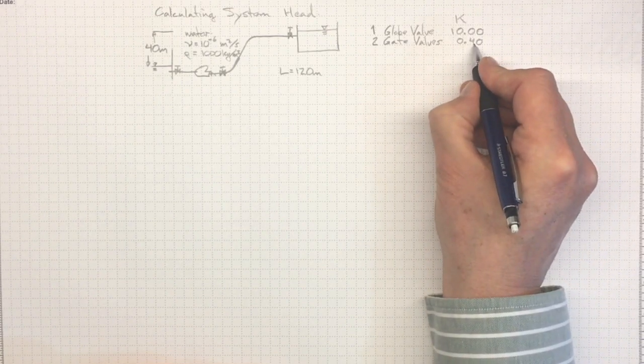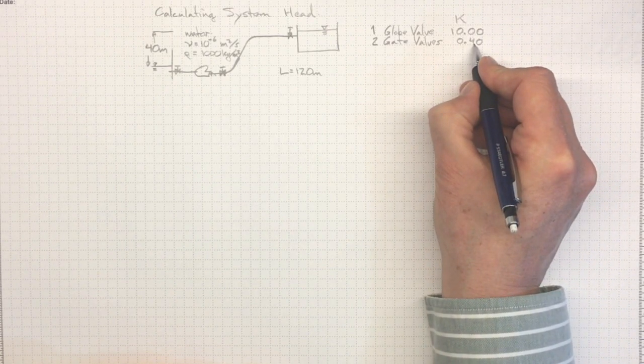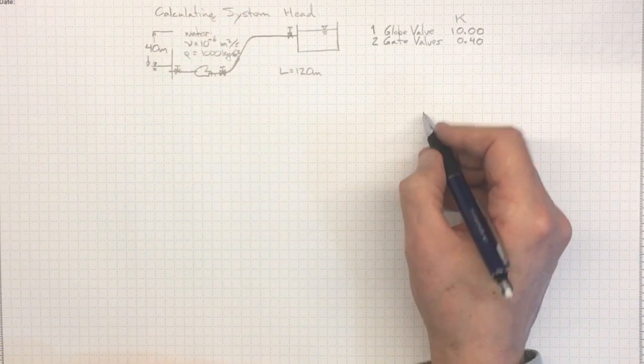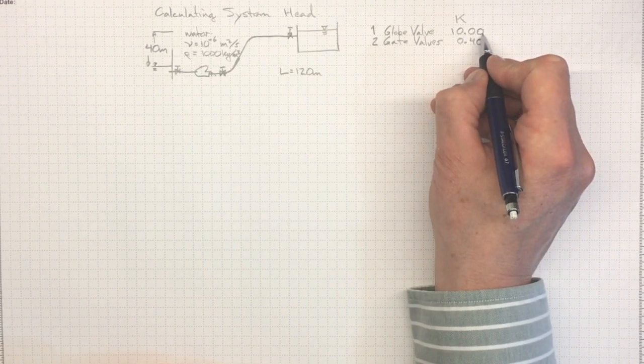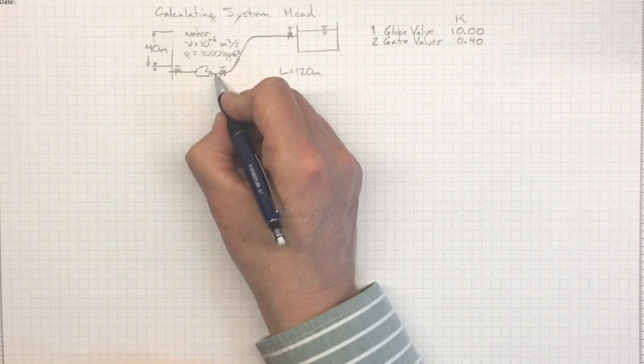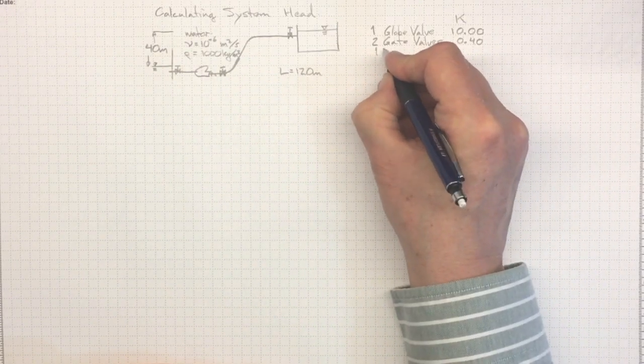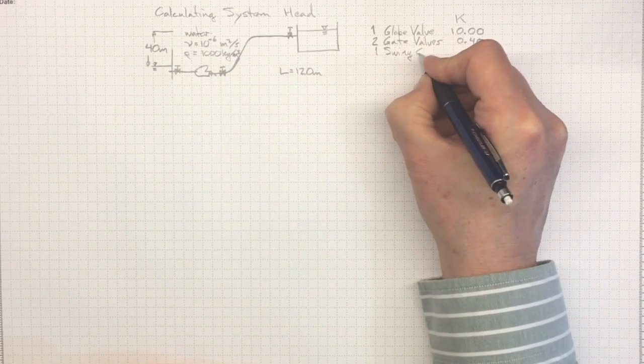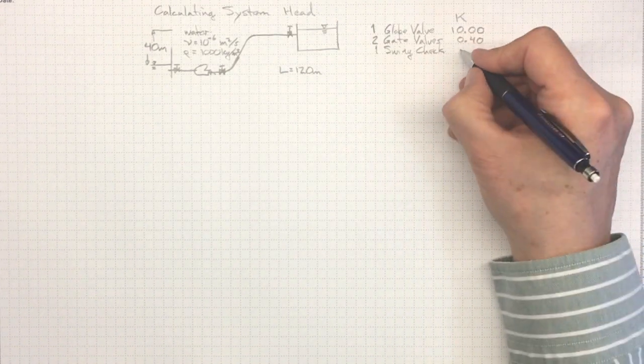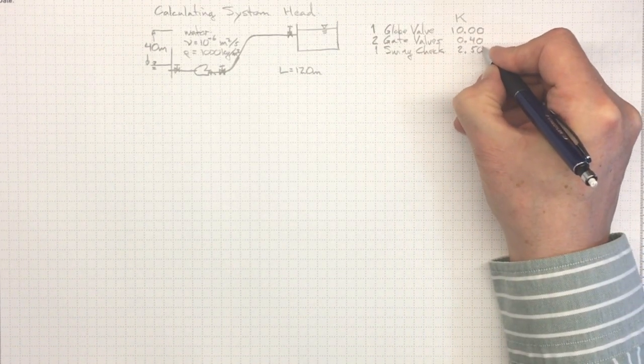Much lower loss across a gate valve, because it just opens wide, basically pulling a gate back out of the pipe, than through a globe valve, which has got much more convoluted passages. We've got a swing check valve here. And its loss coefficient is somewhere in the middle, round about 2.5.